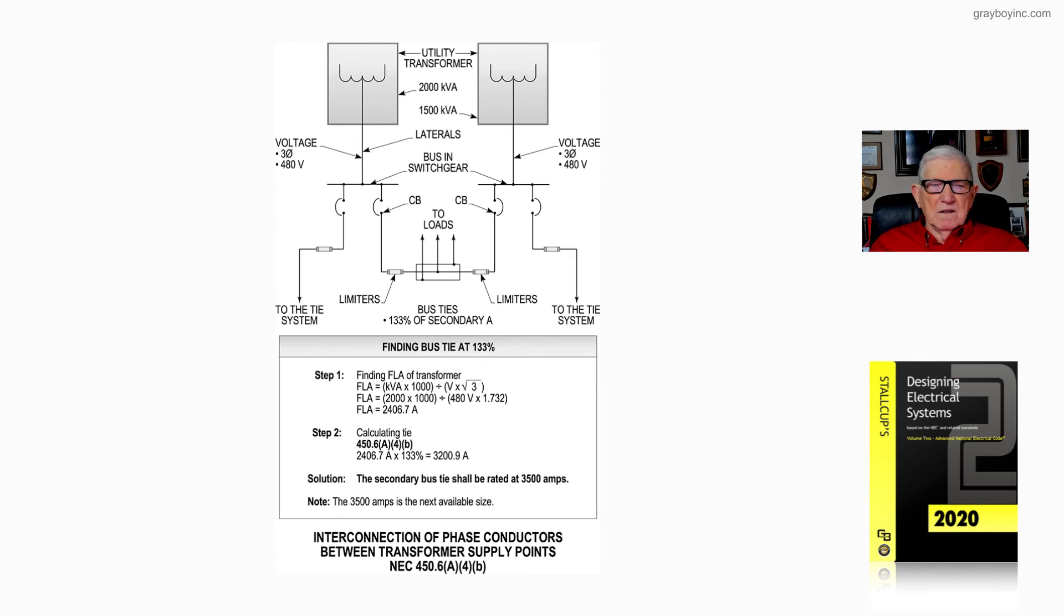And you can see the three taps of those loads coming off of there. Now, that's what this figure 20-17 is illustrating, is the interconnection of the phase conductors between the transformer supply points in accordance with the requirements of 450.6(A)(4)(b).